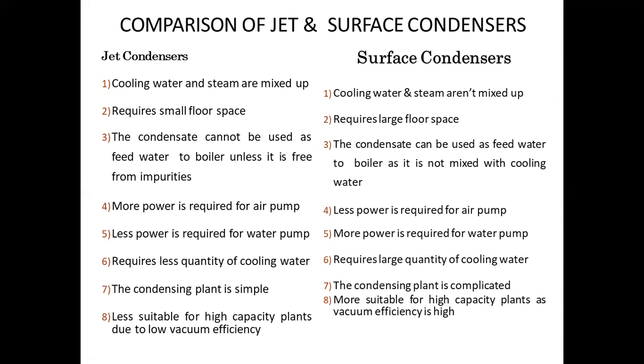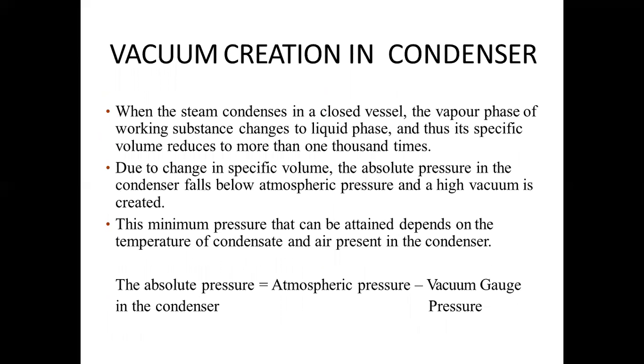Jet condenser plants are very simple, while surface condenser plants are complicated. Jet condensers are less suitable for high capacity power plants due to low vacuum efficiency, while surface condensers are most suitable for higher capacity plants as vacuum efficiency is very high.